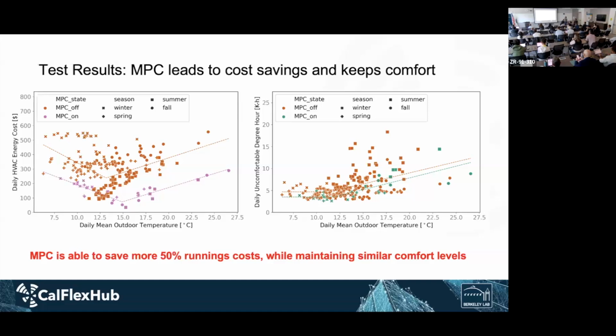And of course, all of this should not come at the cost of comfort. You saw it anecdotally in the day that I showed you before, where the MPC increased the temperature but did not reach the boundary. And this is also reflected in the chart on the right, where the x-axis is the same, and each dot represents how many hours and by how much the temperature in the building was outside the comfort boundaries. For the MPC in green, while the baseline is still in orange, there wasn't much difference. There were only some summer days that were particularly hot, especially last year, like one day where the MPC struggled a bit, but that's also true for the baseline control, and that's a problem of the building itself.